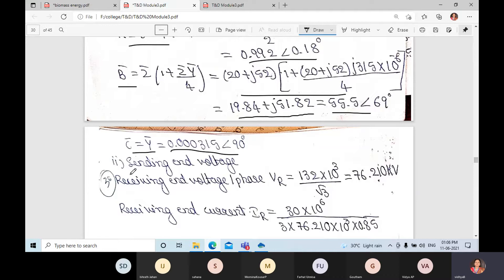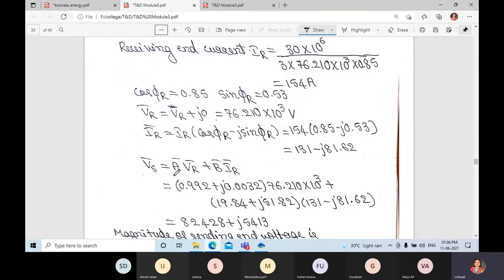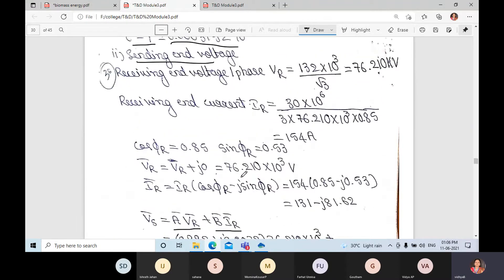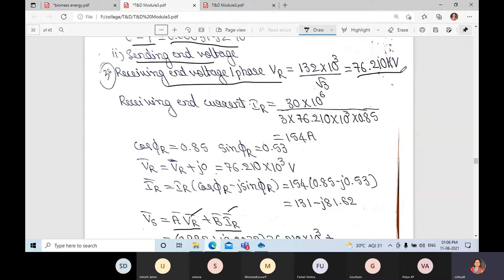The Vs equation is: Vs = A·Vr + B·Ir. Before using this equation, we need the values of Vr and Ir. Since we already know A and B, the receiving-end voltage per phase is Vr = 132 × 10³ divided by √3, which gives 76.210 kV.